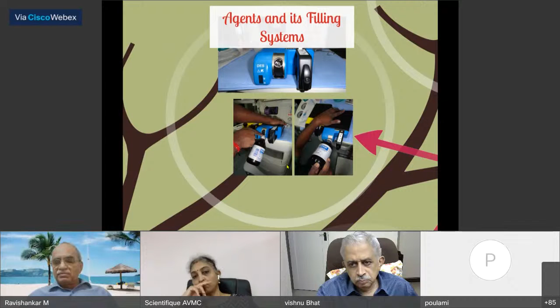So that is what is happening now. And going one step further, they don't want even the agents to spill out when they are filling up the vaporizers. So they have come out with the locks and the nozzles. The nozzle is there in the bottle, and then you have the lock. So you just have to click it on and rotate it so that the agent is filled into the vaporizer, and absolutely there is no leak. And then you just turn it and turn it back. Then the bottle comes out, and there is absolutely no leak in the system. That is how the thing has been advanced.